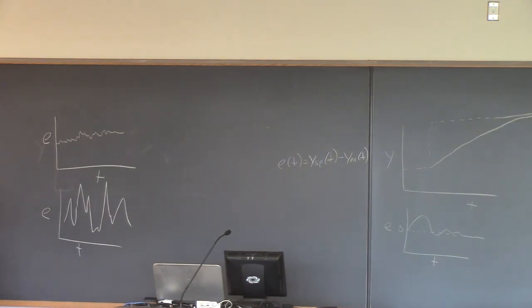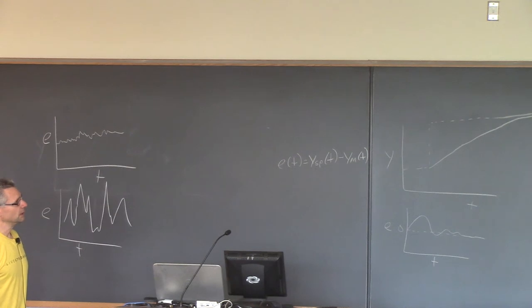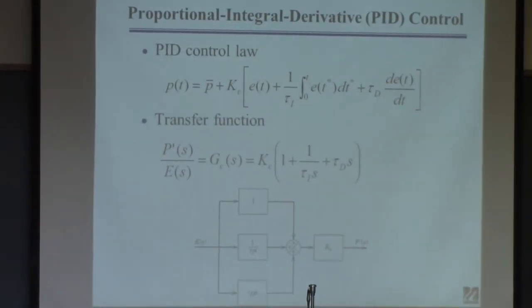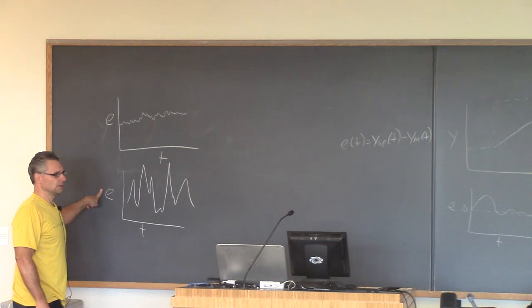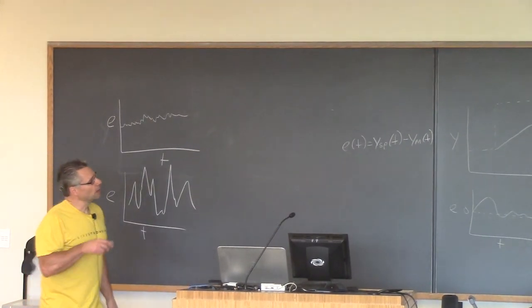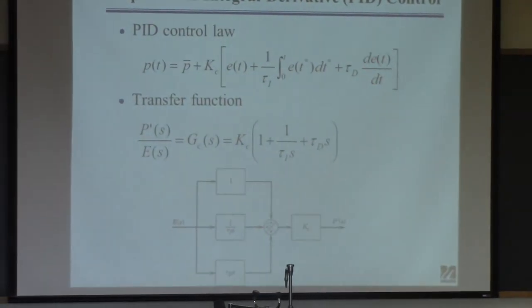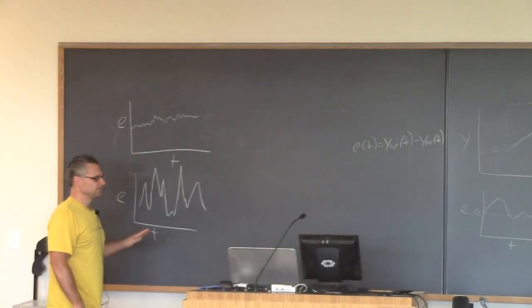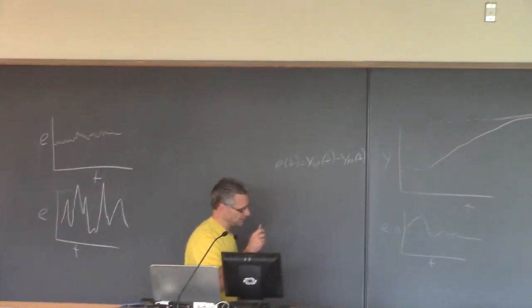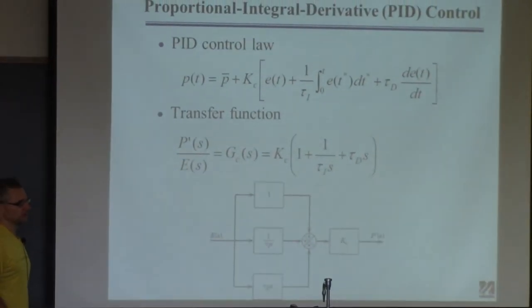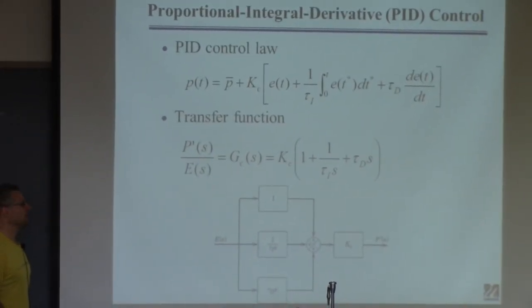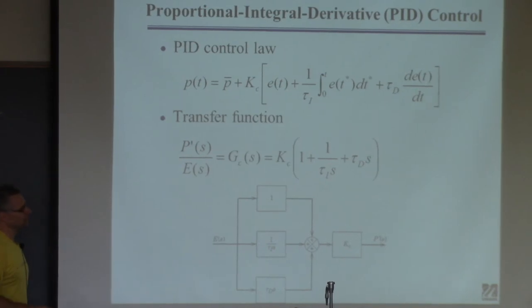My experience is that the benefits of derivative control are usually outweighed by the negative aspects. While it does give you anticipatory capability, unless your signal is really clean, derivative control tends to make controller behavior worse. Engineers usually end up setting τD very small to avoid weighting the noise. In my experience, you can almost always do without derivative control. The critical parts are P and I.